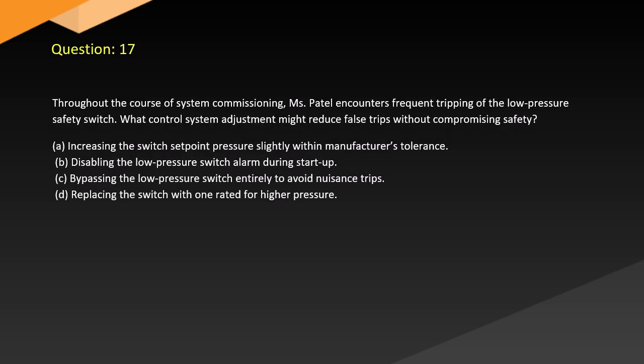Question 17. Throughout the course of system commissioning, Mr. Patel encounters frequent tripping of the low-pressure safety switch. What control system adjustment might reduce false trips without compromising safety?